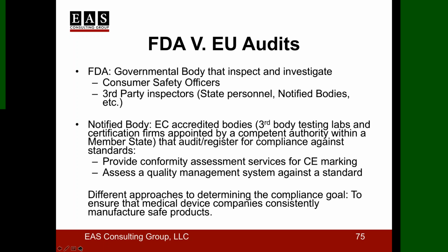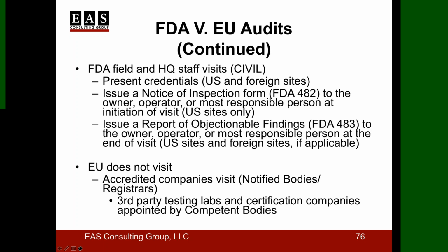Notified body, basically, they're accredited to do not only the audit part, but also they give the approval for product and process. They issue certifications, whereas someone that's a registrar doesn't do that. Here it just says, yes, you do or you don't meet EU or ISO 13485 or whatever the case is. Again, there's different approaches to them. Like I said, FDA uses the QSIT booklet when they do routine type of inspections.